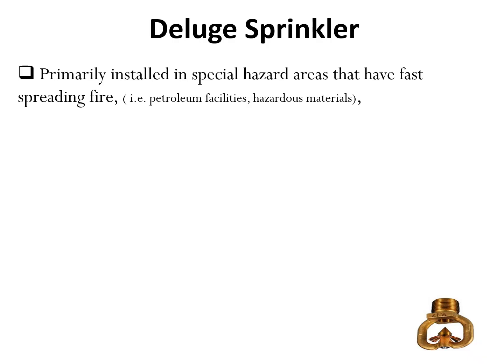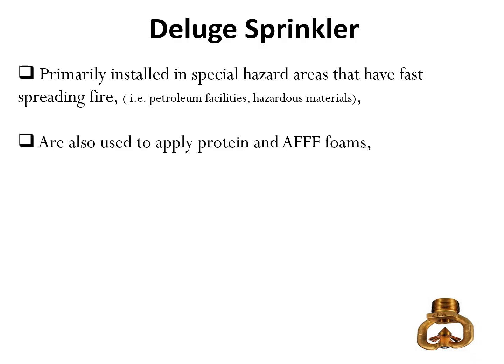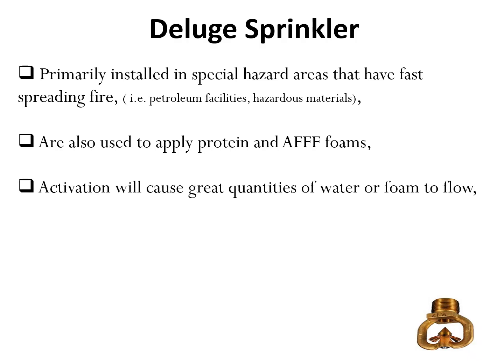Dear friends, the deluge sprinkler systems are provided in special hazard areas that have fast spreading fire, that is petroleum facilities, hazardous material, and electrical apparatus, and also used to apply protein and triple F foams. We'll discuss them. Activation will cause great quantities of water or foam to flow. It usually requires several detectors to activate before discharging.